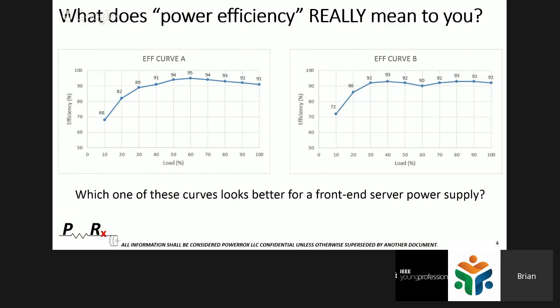In reality, most servers — even high-end ones — if they share across more than two power supplies, their load shifts more towards the left side of these efficiency curves. The optimal place for just about any network power supply is actually in the 20% to 40% load range. The takeaway is that Curve B will actually have a highly significant power savings in dollars over time for high-end servers than Curve A, even though Curve A has a higher peak efficiency.